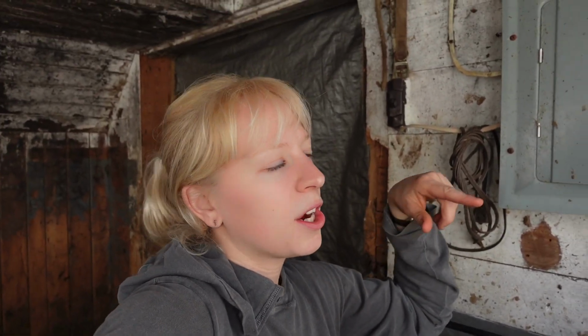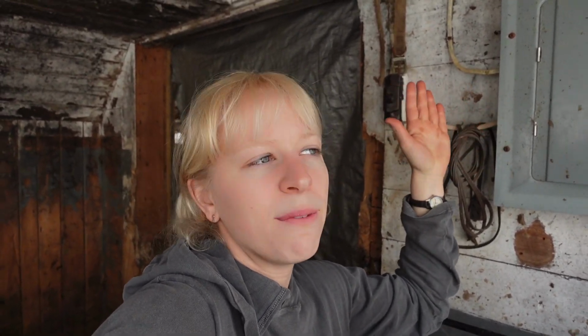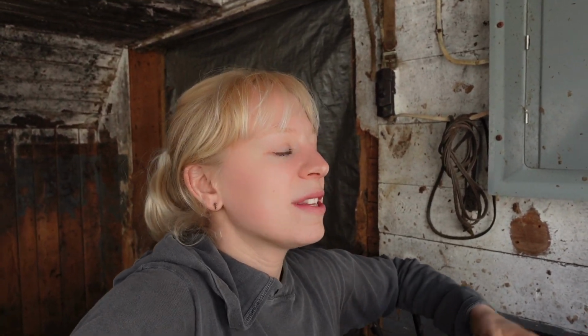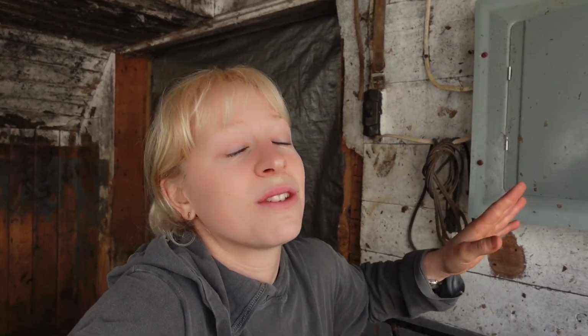So he reset that breaker, and that should have made the other fan start working. Obviously, this one down here wasn't going to because it was burnt out, but that one still wasn't working. So we were really confused about that, so he was checking all the electricity around it, and he said it should be working, it should be fine. Well, come to find out, just by complete coincidence, those stab-ins in there, apparently every once in a while you have to clean them, or just stick them in and pull them out like 1,000 times and then it will start working. Well, apparently that had for some reason at the same time decided not to work. So that was kind of a coincidence, but once he did that a few times, it did start working and nothing was tripping any breakers after that, so that was good.